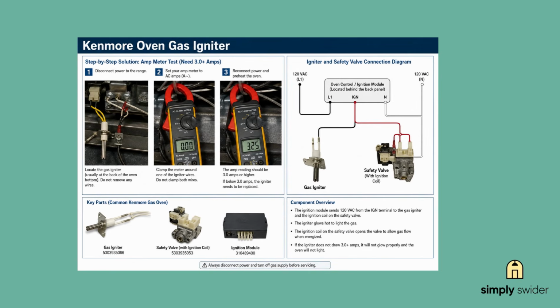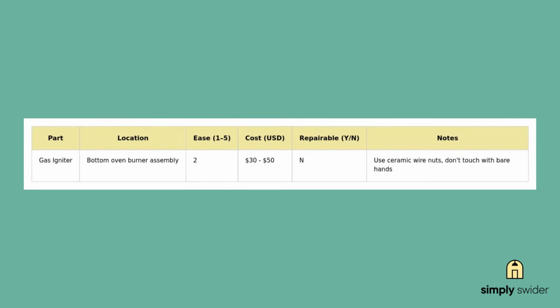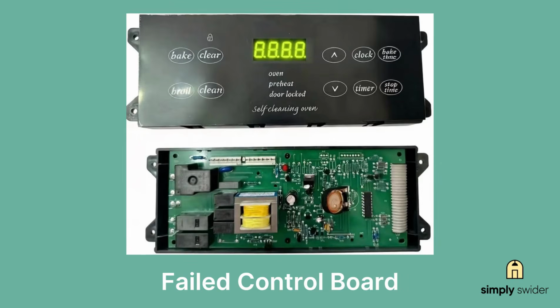This is where most people mess up. They see that bright glow and assume the igniter is fine, so they go and spend $150 on a new gas valve when a $30 igniter would have fixed it. I've seen this countless times. The igniter looks perfect, but those silicon carbide elements just thin out over the years until they can't do their job anymore. You'll see error codes like F1 or F11 flashing, or maybe the display works, but there's no voltage getting to your heating elements.